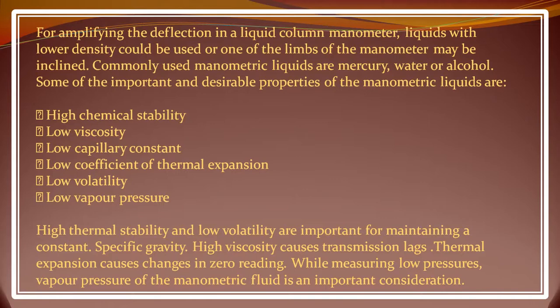Low coefficient of thermal expansion is important because a high coefficient can change the fluid level and give incorrect readings. High viscosity causes transmission lags — if the fluid is highly viscous, there is a lag between input and output. Thermal expansion can also cause a change in the zero reading, defaulting the zero. When measuring low pressure, the vapor pressure of the manometric fluid is an important consideration.